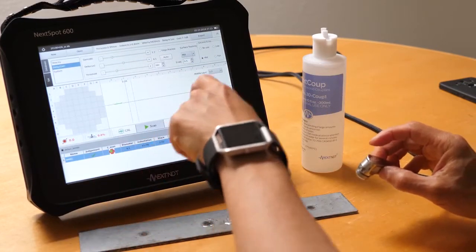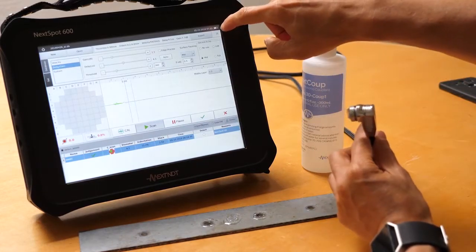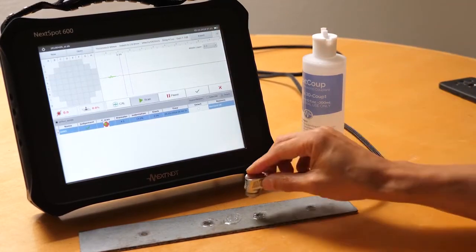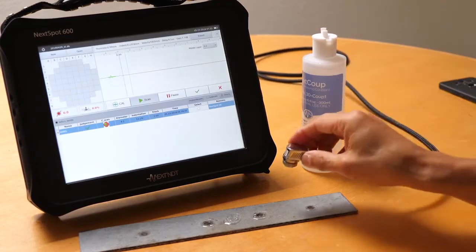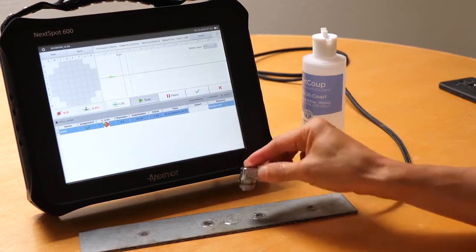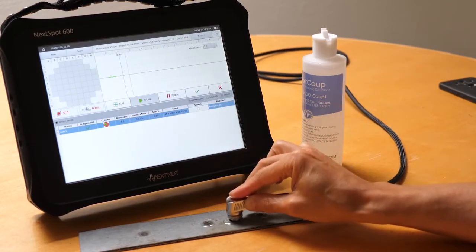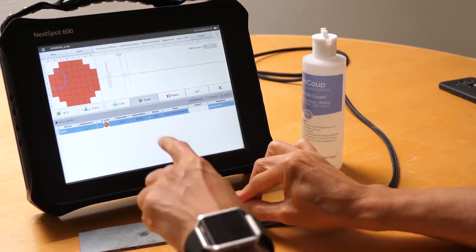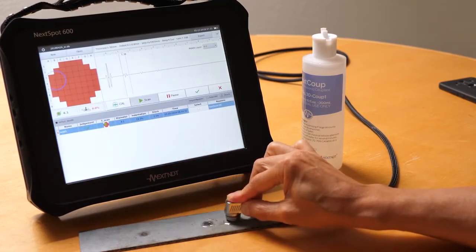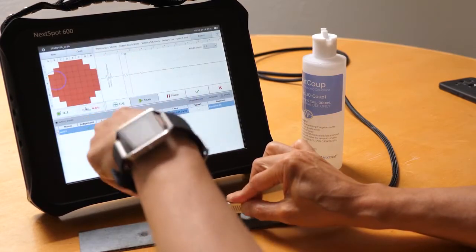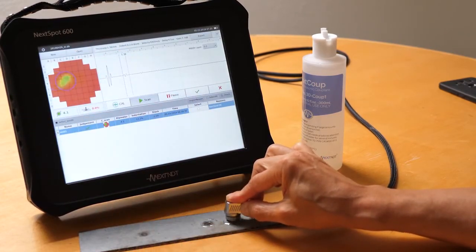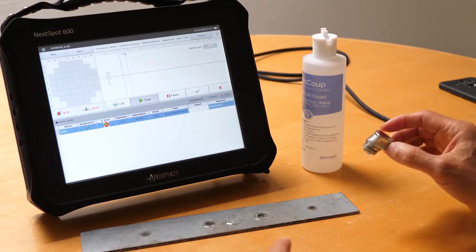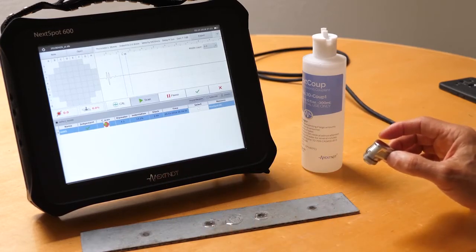And lastly, I'm going to move this up. I'm going to put the transducer on the plate where there's no spotweld and I do a final calibration and make sure everything is red. And then I can start the scan.